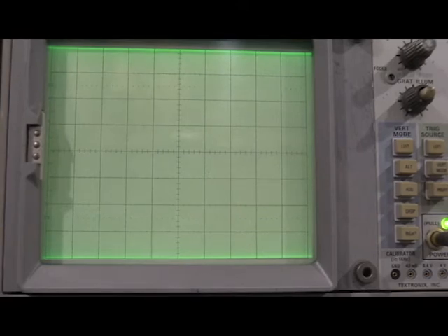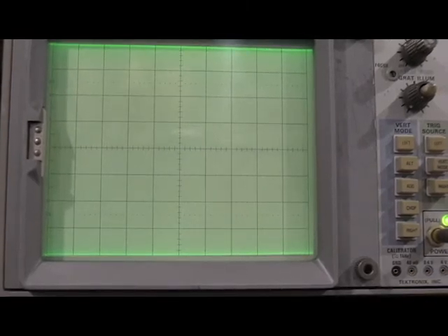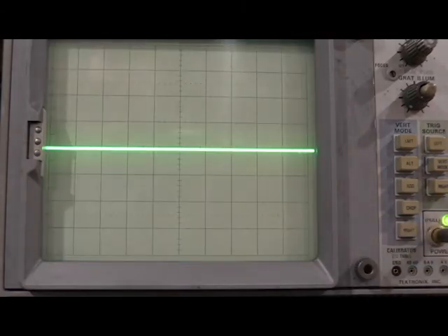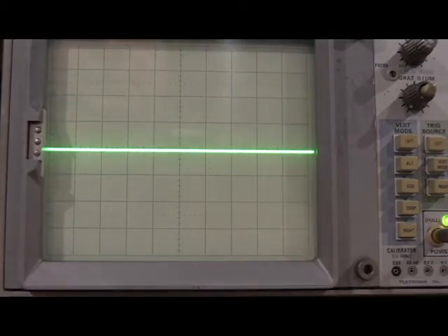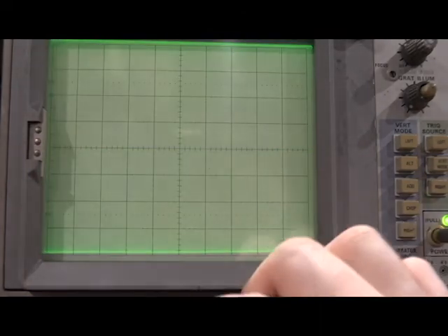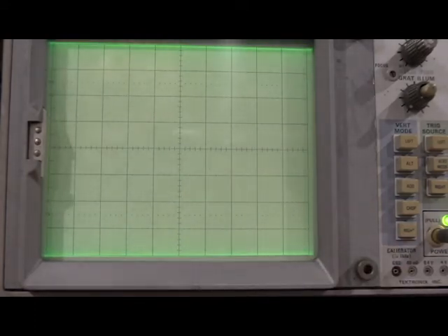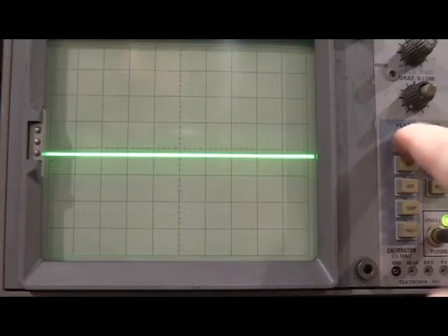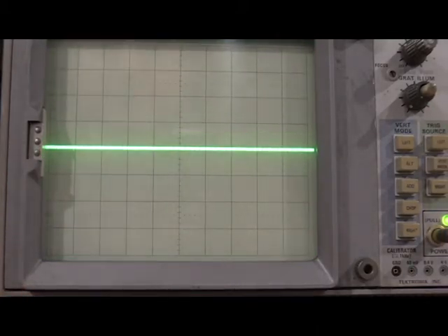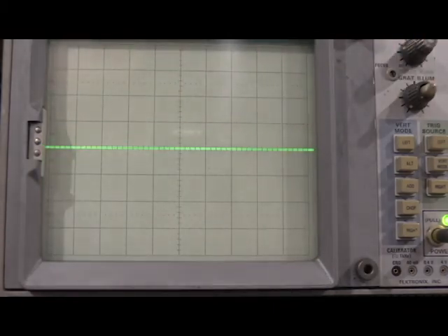This is checking the rejection between both channels. They should be attenuated 100 to 1. So we have 8 divisions of display fed into the left side, and we'll switch to the right. And we have no signal on the right, which is what we should have. I gotta reverse it, and then we'll do the other way. So we have 8 divisions of signal, and I will switch over to the left, and we have no signal to speak of on the left. So that is vertical amplifier isolation working perfectly.